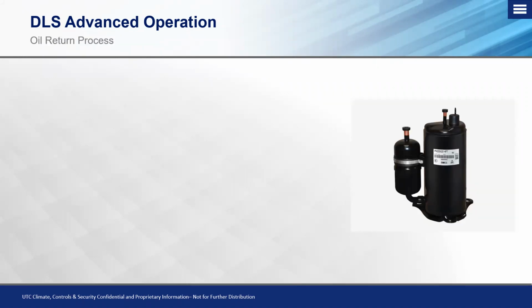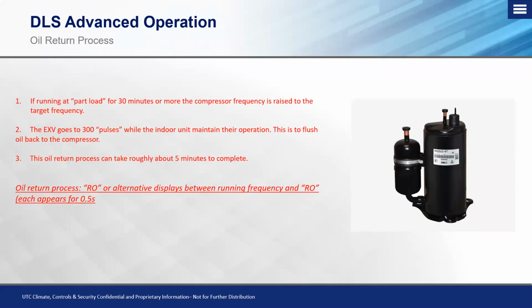All right, so we look at this compressor on here and we say, okay, you know what? I'm not really getting how the oil recovery process works. So let's break it down as basic as we can. If we're running at part load for 30 minutes or more, the compressor frequency is raised to the target frequency or higher, depending on what it needs to be at. The EXV goes to 300 pulses while the indoor units maintain their operation. Again, this is to flush that oil in the system back to the compressor so that we're not starving them. This oil return process can take roughly about 5 minutes to complete.